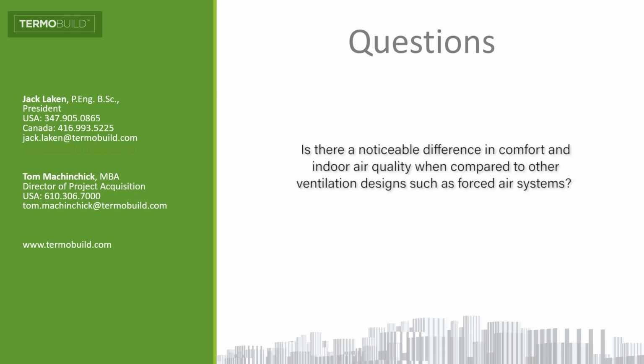Is there a noticeable difference in comfort and indoor air quality compared to other ventilation designs, such as forced air systems? Yes, there is. The reason is that our prime time is nighttime—we leverage the difference in energy between night and day, as well as the fact that outdoor air quality at night is considerably better than during the day. What's happening is the nighttime freshness is brought into the building. In a medical building, when people walk in, in the morning the indoor air quality is better than outside, and they're quite pleased with the noticeable difference.